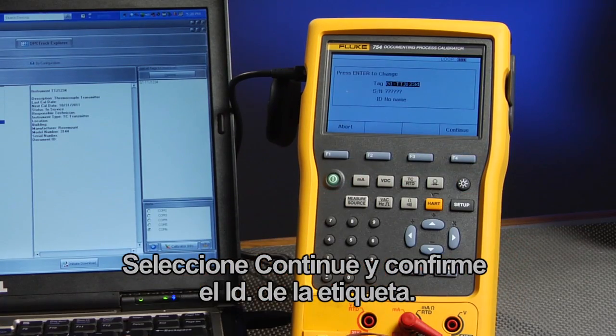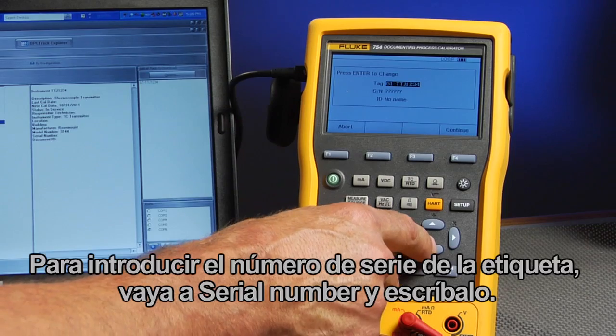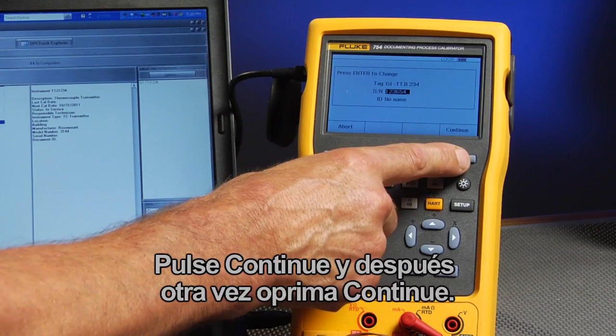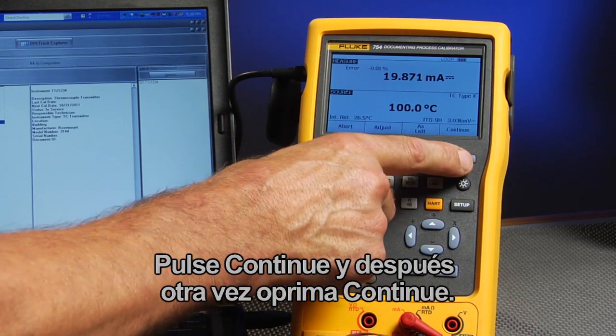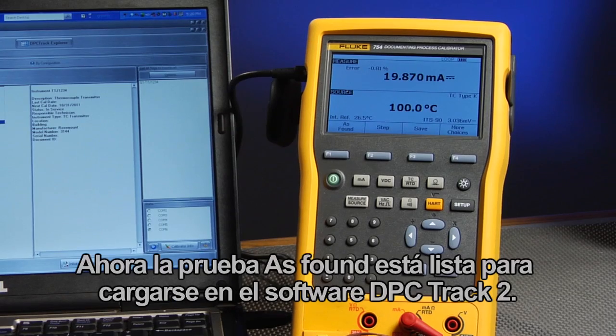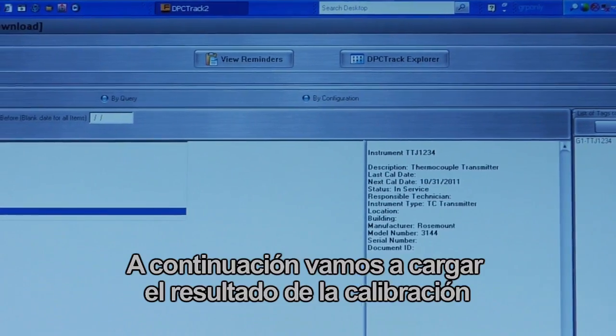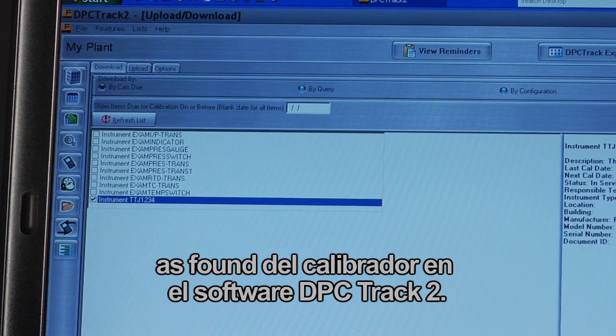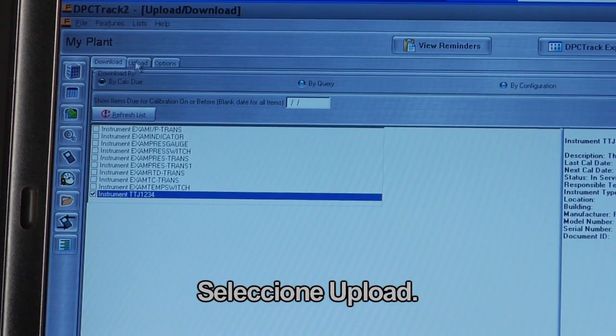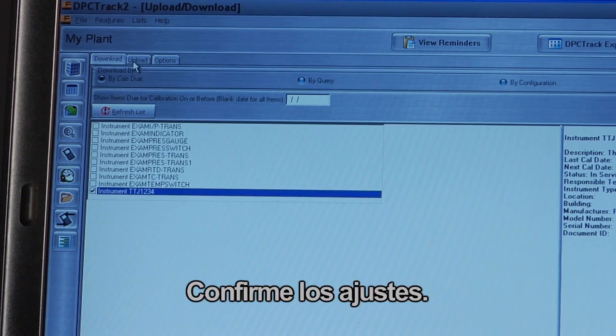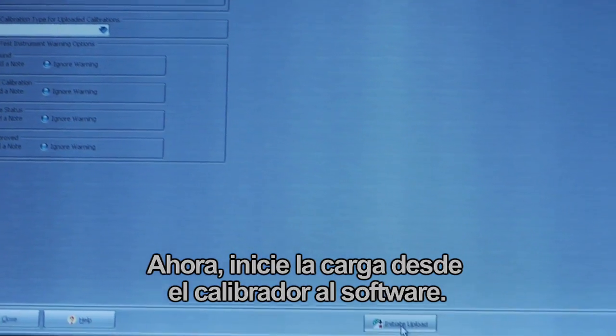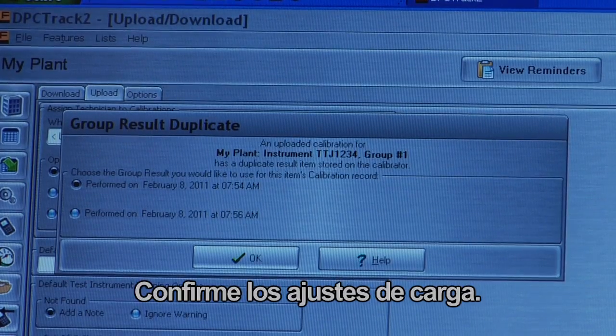Select Continue and confirm the tag ID. Move to Serial Number and type in the serial number of the tag, then continue. The as-found test is now ready to upload to DPC Track 2 software. Select Upload to upload the as-found calibration result from the calibrator to DPC Track 2 software. Confirm settings, then initiate the upload from the calibrator to the software.